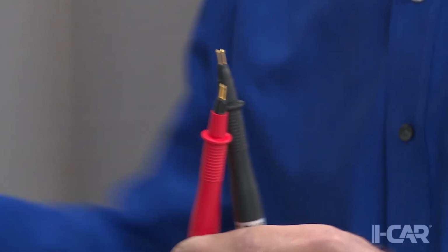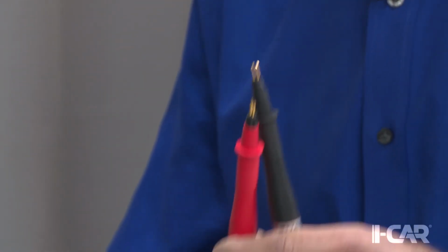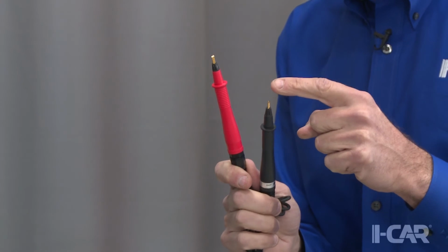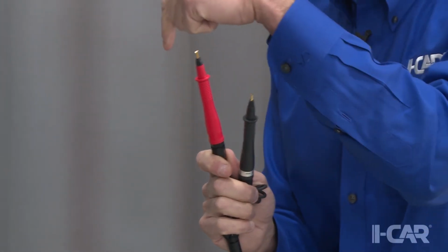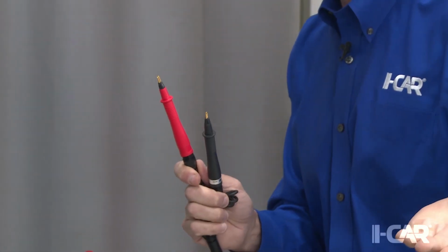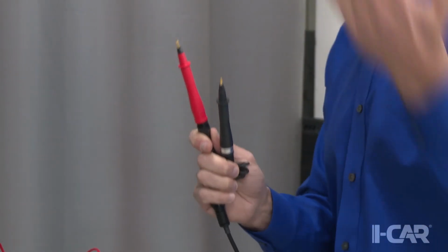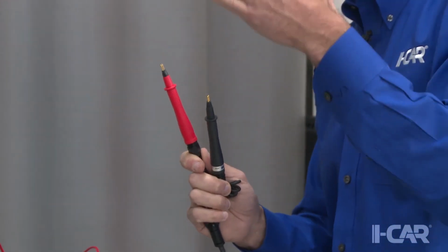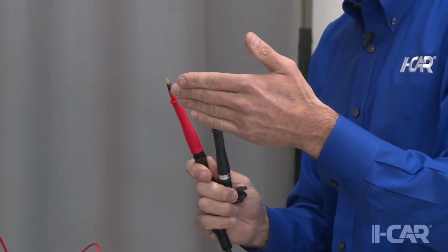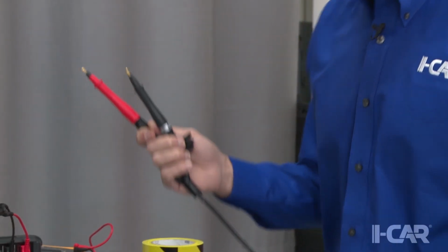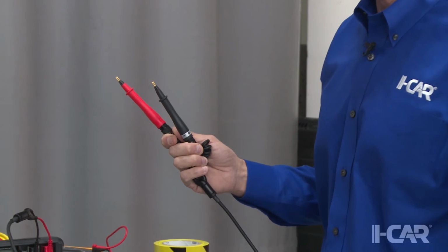So now my thing is not holding anymore. Okay, I have 2 terminals. One is applying 1 amp, goes to the other, and the other one is a voltmeter. So now we have amps and we have measuring volts. We know current, 1 amp, we measure the resulting voltage. So now, using Ohm's law, we can calculate. And that meter does it internally very accurately, for that money.